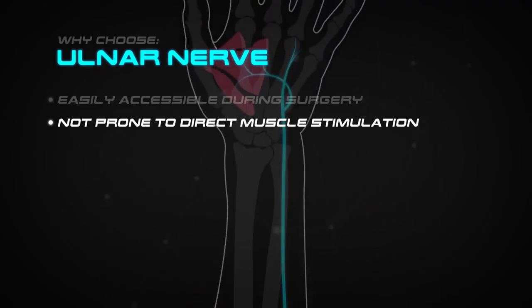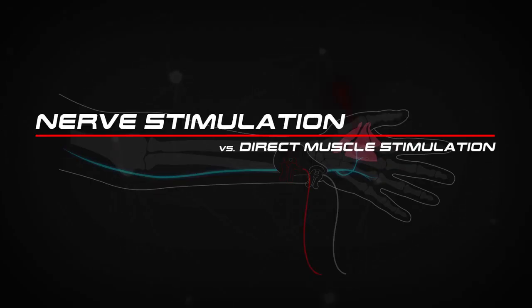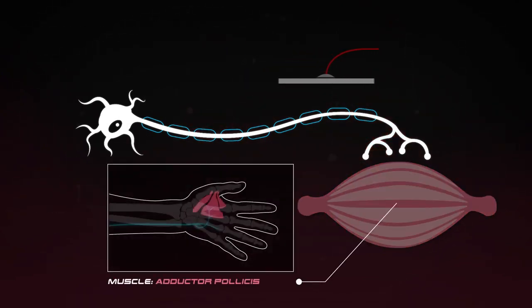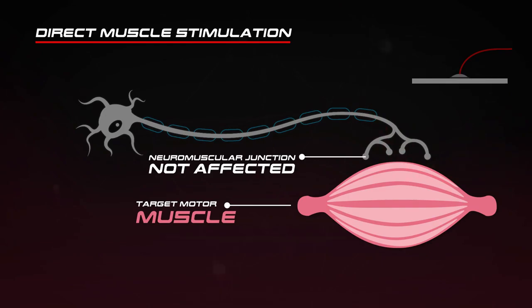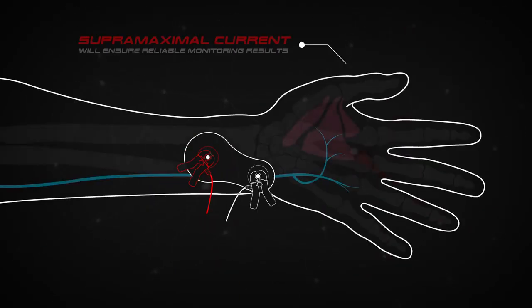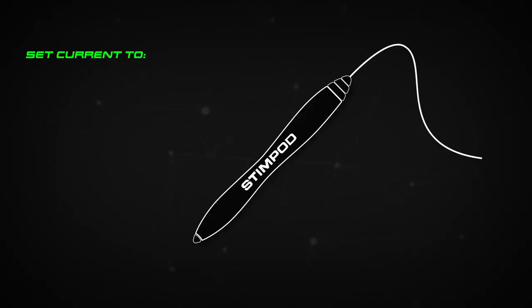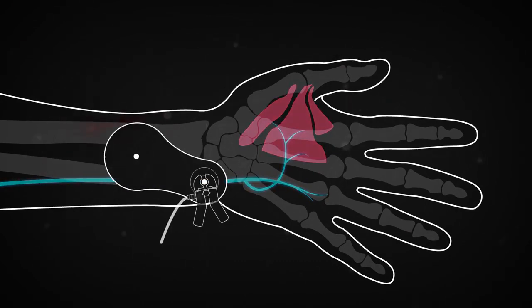In anesthesia, neuromuscular blocking agents may be required to facilitate endotracheal intubation and provide optimal surgical conditions. When neuromuscular blocking agents are administered, neuromuscular function of the patient must be monitored. Neuromuscular function monitoring is a technique that involves the electrical stimulation of a motor nerve and monitoring the response of the muscle supplied by that nerve.